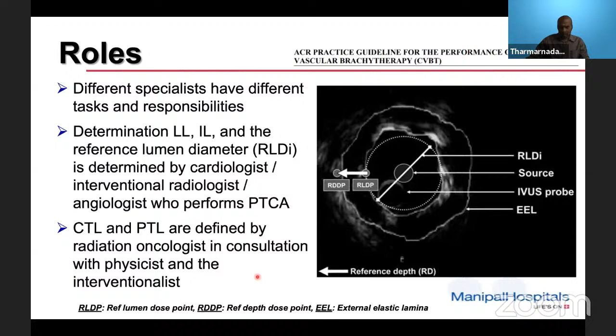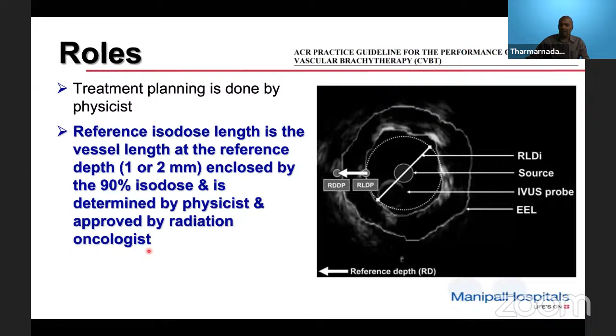The treatment planning is done by the physicist once these dimensions are given to the physicist by the interventional radiologist. Treatment planning, or in other words computing the treatment time, should be done by the physicist. Basically, the physicist will calculate the reference isodose length. Reference isodose length is the vessel length at the reference depth, which is 1 or 2 mm from the lumen, as we had seen earlier, 1 mm for coronary and 2 mm for peripheral artery. So that is the vessel length at the reference depth enclosed by the 90% isodose line, and it is determined by the physicist and shall be approved by the radiation oncologist before the treatment is administered to the patient.